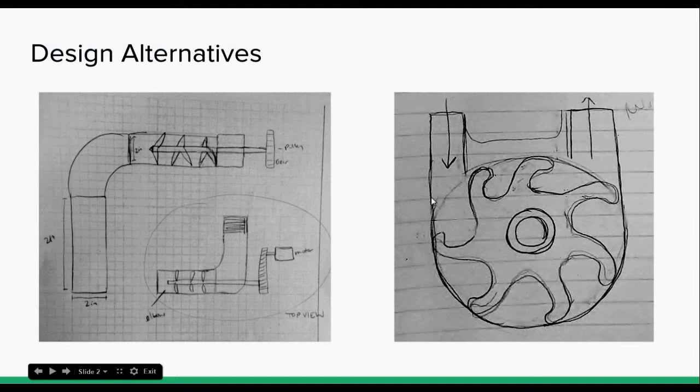And radial pumps, after some research we found, are generally good for situations where you need more head and a lower flow rate, so we didn't think that would be suitable. And then axial flow pumps are generally good for situations that require low head and a higher flow rate.